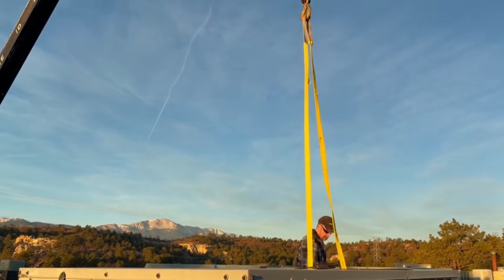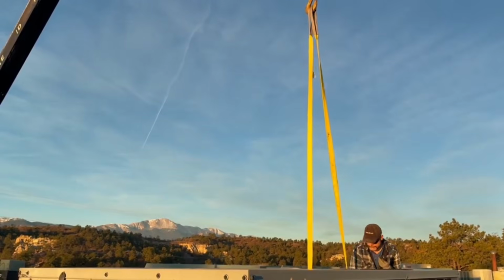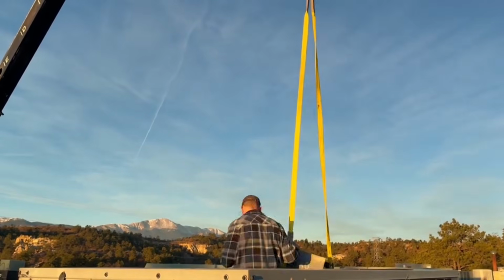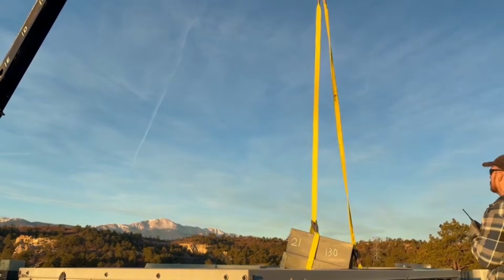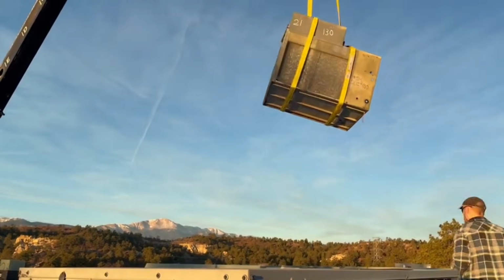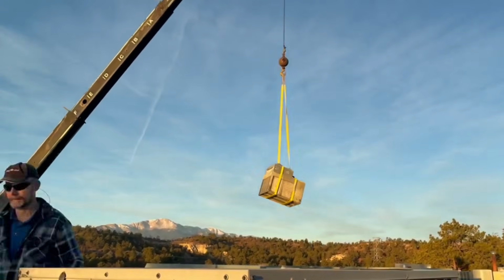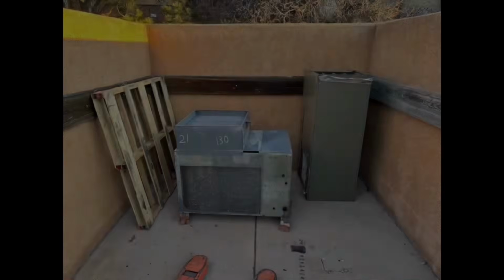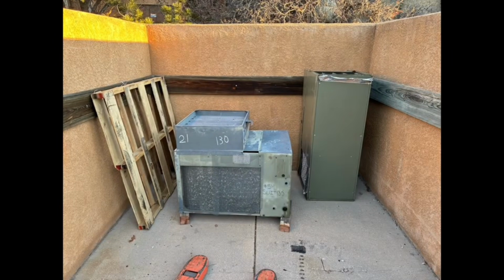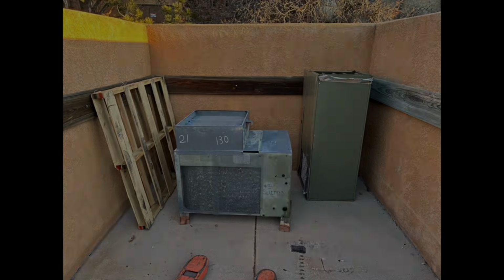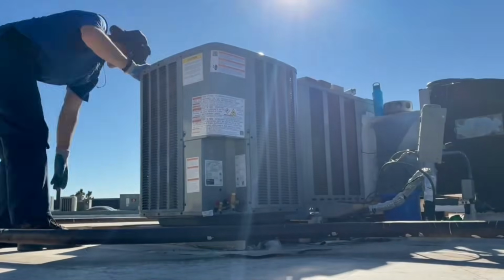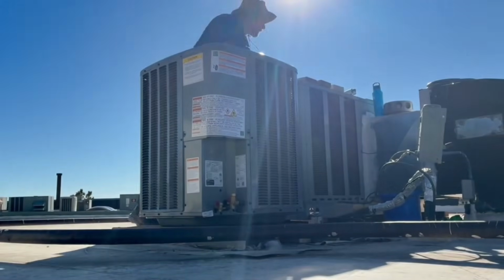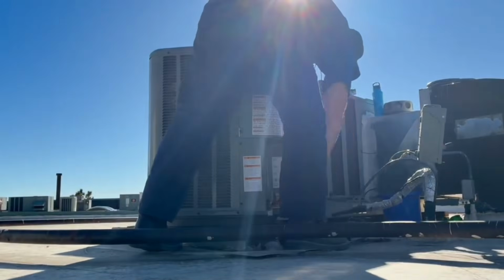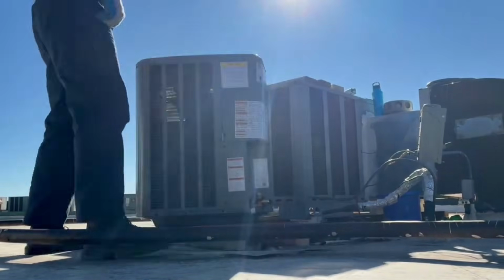So I usually try to disconnect the old system on the roof the day before. That way the following morning it's ready to lift off for the crane. There we go. There's the old equipment ready to haul away. Refrigerant's been recovered out of the system. So we'll place the new condenser unit where we need it. And I need to position it so the existing refrigerant line set can line up with it. That's important.